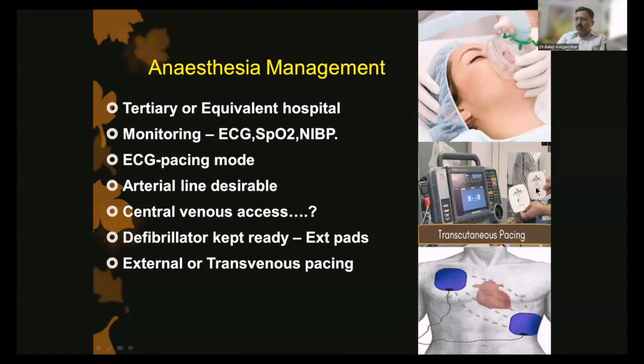You just have to put the two leads like this and start the current. Obviously, the current requirement is more because the current has to travel from the skin up to the heart. Maybe 70 milliampere or 80 milliampere current is required to pace the heart. This is a very, very important facility, and one must have it in the OT.